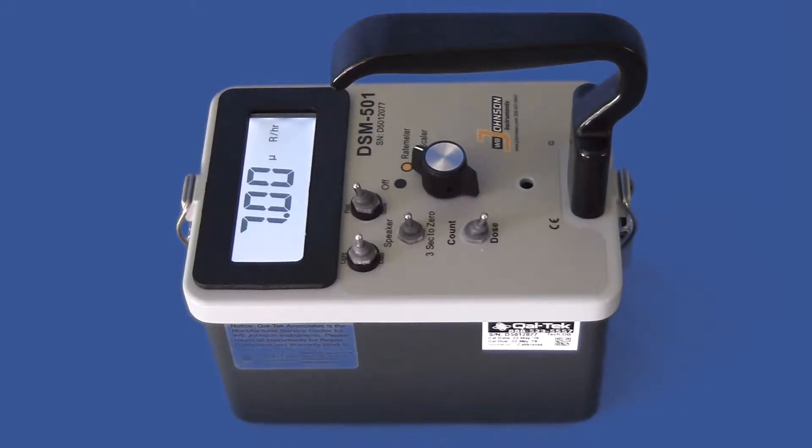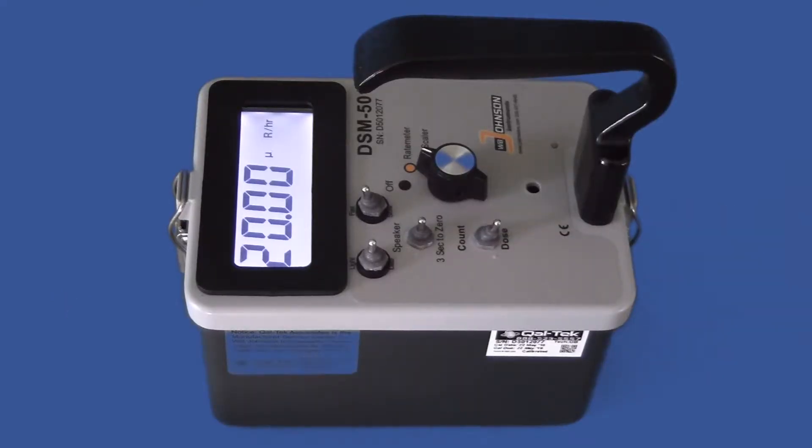At this time, we are detecting background radiation, which appears to be about 6 to 7 microroentgen per hour. We will test the response of the DSM-501 with a 10 microcurie cesium-137 source, spaced at about 2 feet from the detector window. Right now it is reading about 17 to 20 microroentgen per hour.